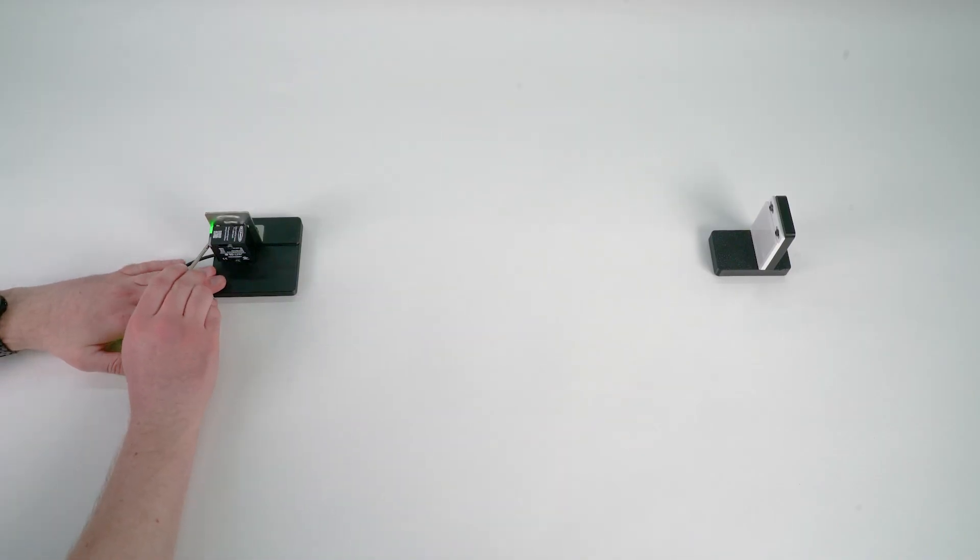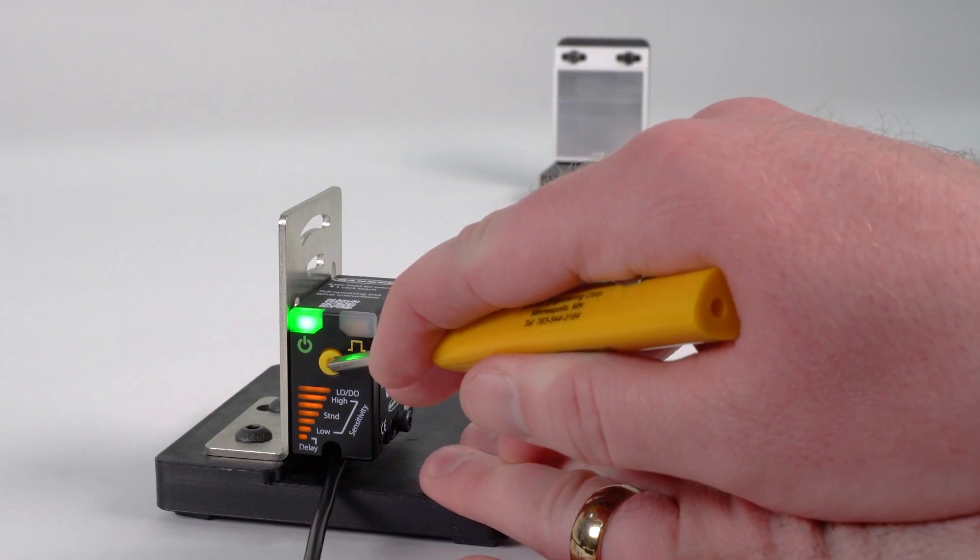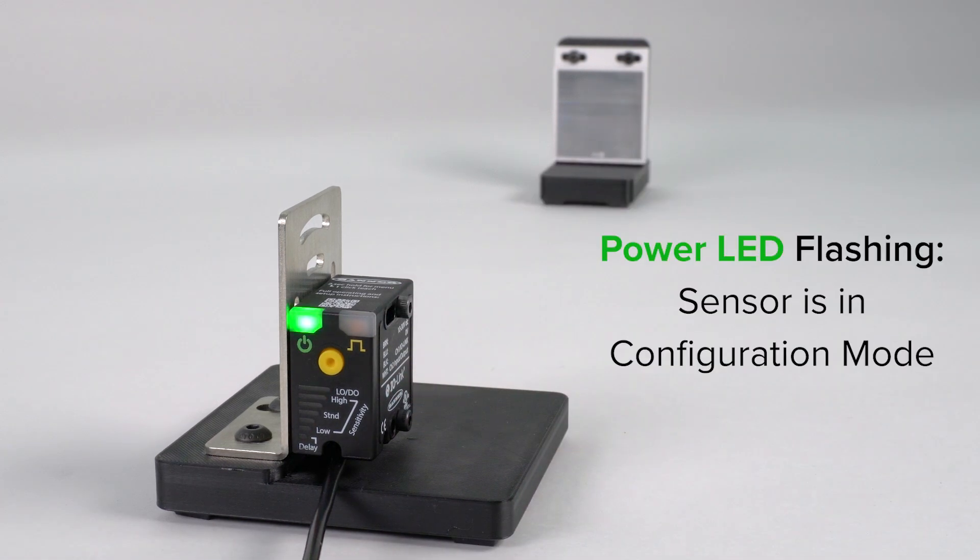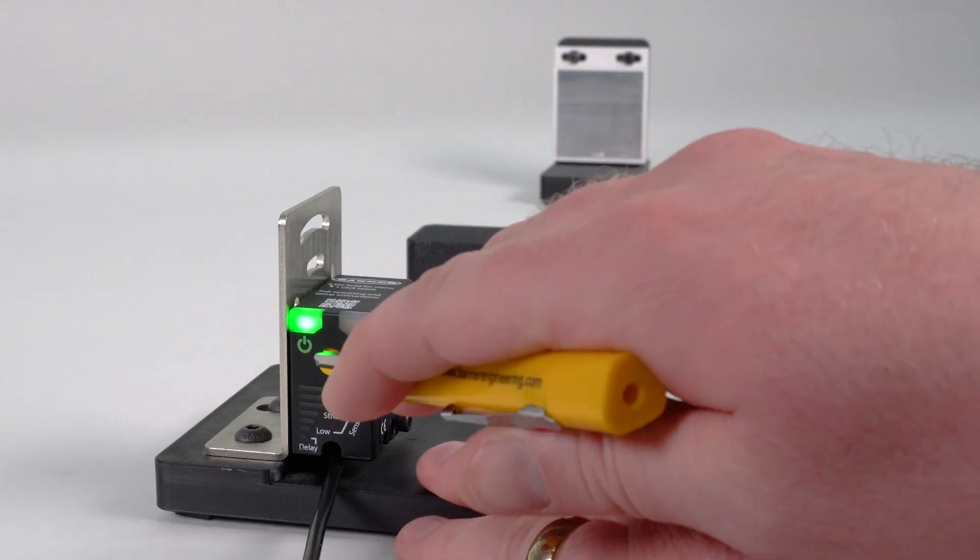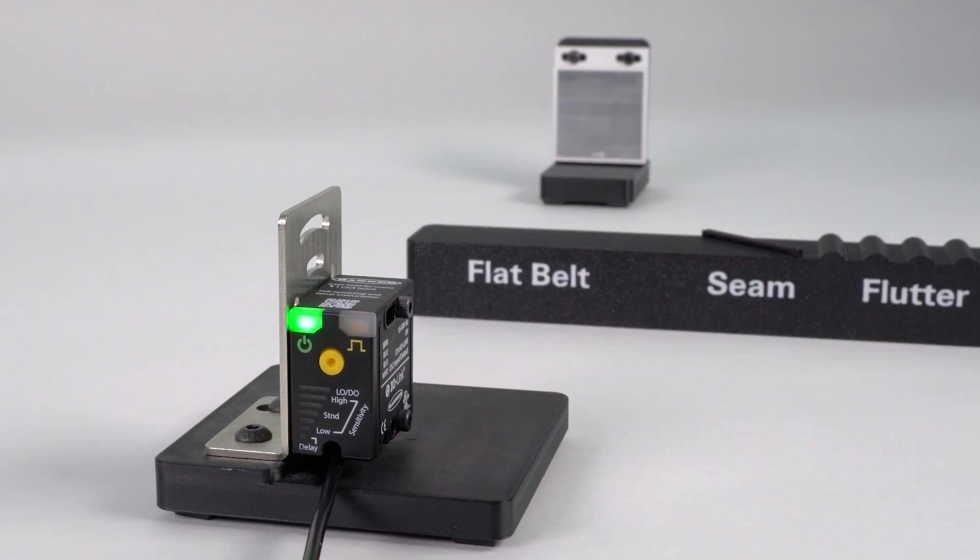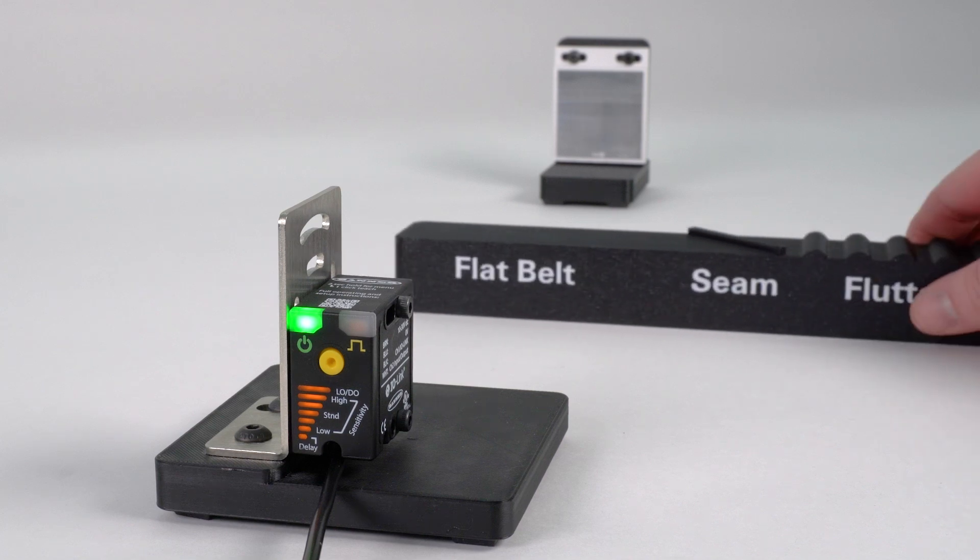Begin by pressing and holding the teach button for two or more seconds until the green power LED starts flashing. This puts the sensor into configuration mode. Present the normal condition to be filtered out and press the teach button once. The green and amber LEDs will flash twice to confirm the taught condition has been accepted and the sensor will return to run mode.